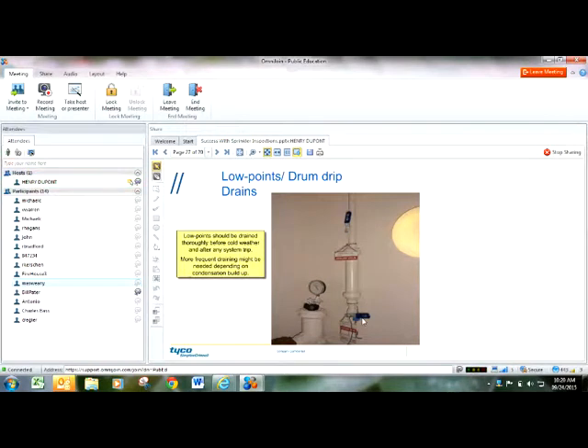But what happens is people think their sprinkler systems don't require any maintenance, or they just become invisible after a amount of time, and they don't drain these low point drains. So what happens with this top ball valve shut, that condensation or whatever trapped water might be in the dry pipe sprinkler system starts to collect on top of that top ball valve until it goes up into the attic area, and there's no heat in the attic. So as soon as it gets good and cold out, it breaks right up there above the ceiling in the attic. And I'm betting we do 40 or 50 service calls a winter on that exact scenario. People aren't purging these drains and they freeze and break. And then they're shocked when they see how much water comes shooting out of a piece of 1 inch or 1.25 inch pipe that was meant to be a drain in their building.